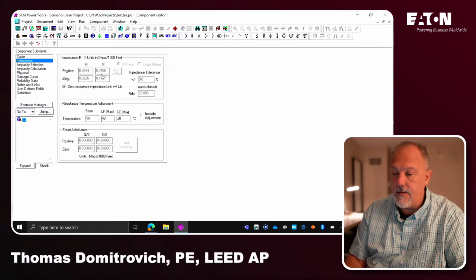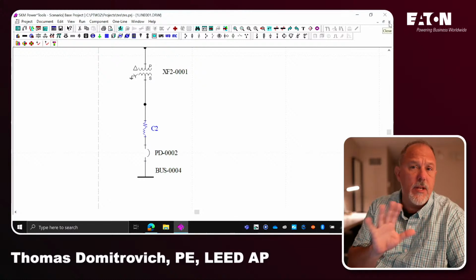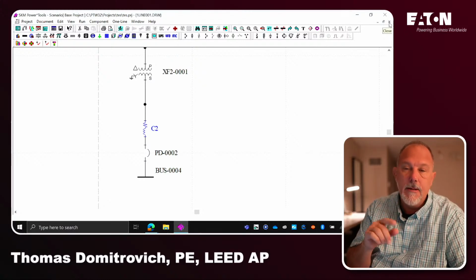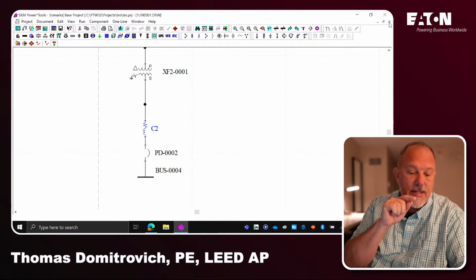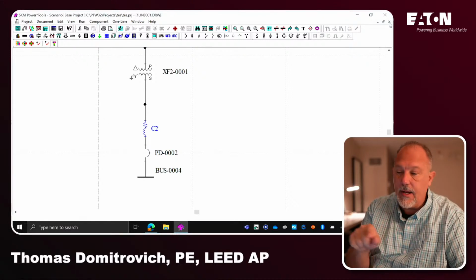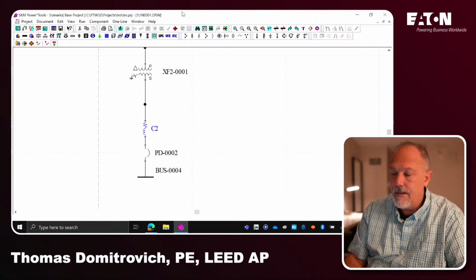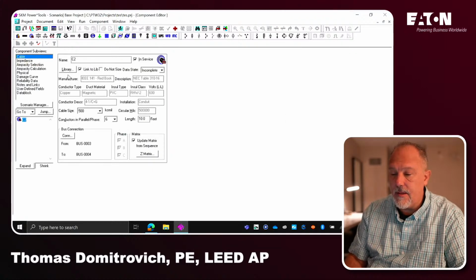And I'm reading that right here. That's your R and X in ohms per 1,000 foot. So I'm good with that. I'll just leave the impedance values. They're a little different, so we know we're not going to get exactly the same numbers. If I wanted to use the exact numbers, 0.029 and 0.048, I would go in and edit that library and edit that conductor. You know what? Let's do that. I can't remember how to do that, though. I linked the library. Oh, I'm going to uncheck that. And then I'm going to go to impedance.